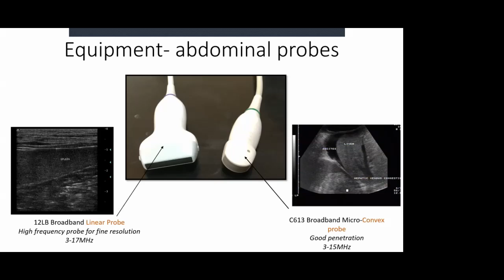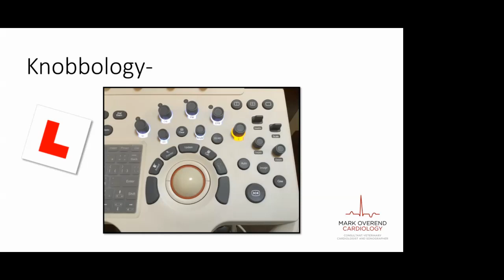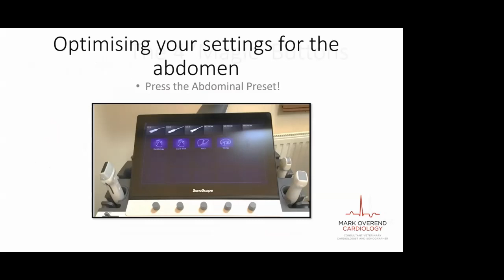And then for all you learner drivers out there driving your ultrasound machine, I think it is really important to be able to understand how to drive your machine, what all the buttons do. So I think your starting point, at least when you're doing an abdominal ultrasound scan, is select your probe like this, and then tell the machine that you're doing an abdominal ultrasound scan. You don't want to be using an echo setting to do an abdominal ultrasound scan. Sounds really basic, but it's so important that you do select things properly, because it makes a huge difference to the quality of the imaging that you can do.